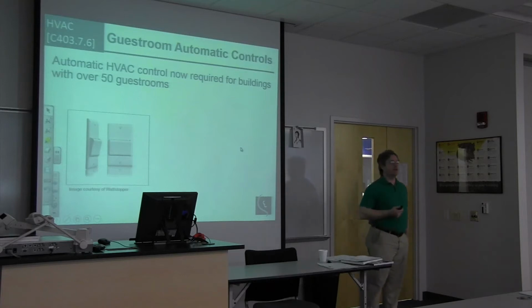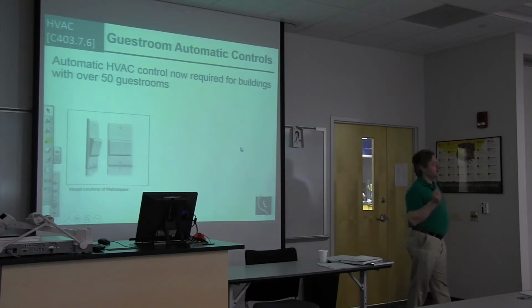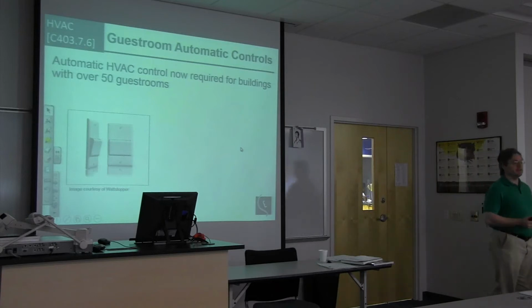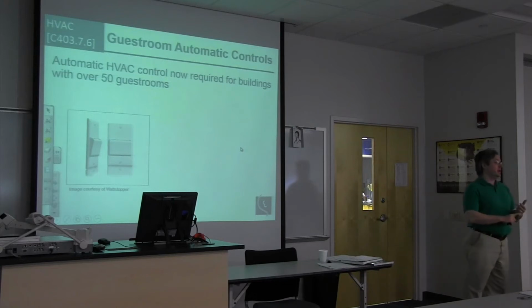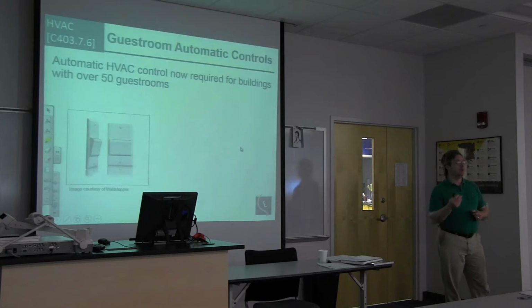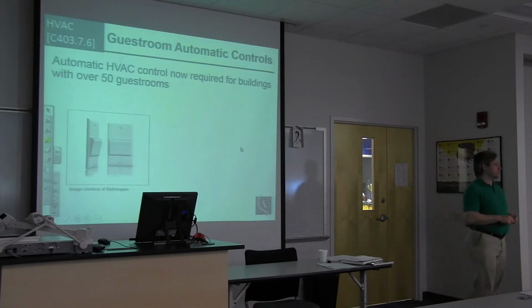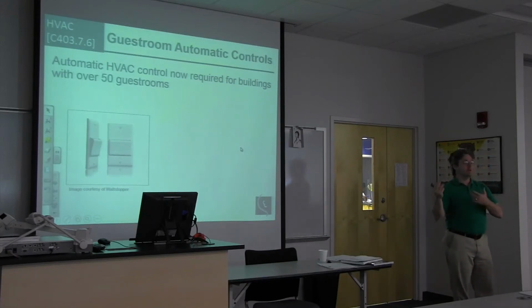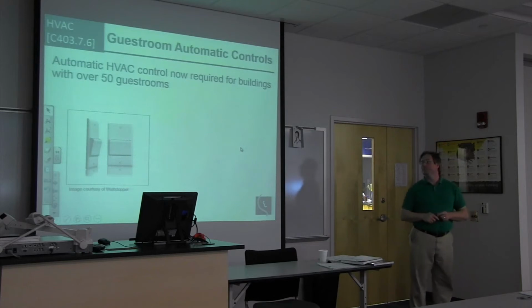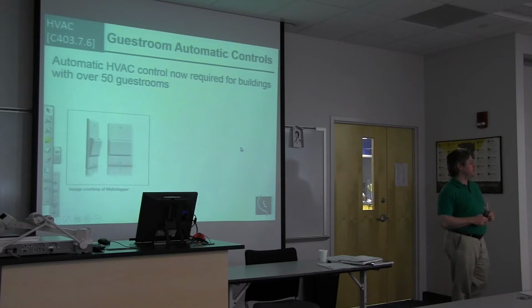Guest room automatic controls. This can either be done locally within the room. This is one way to do it that I've seen, where you just drop your key card in and it turns on. Typically it'll enable the lighting in the room, and it'll turn on the HVAC for you. Or you can do it via a centralized guest control system, where the front desk, when you log into your room, says, oh, okay, there's someone here, go into occupied mode. But that's now required anytime you have buildings with 50 guest rooms or larger.